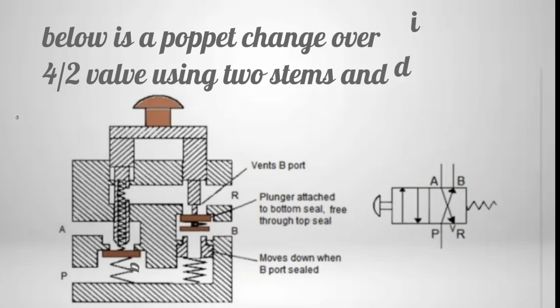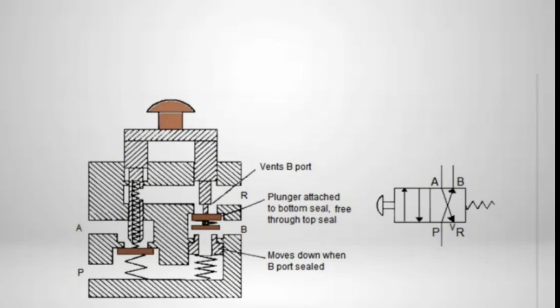Below is a poppet changeover 4-way valve using two stems and disc valves. When the push button is released, A and R ports are linked via the hollow left-hand stem, and P and B ports are linked via the normally open right-hand disc valve.